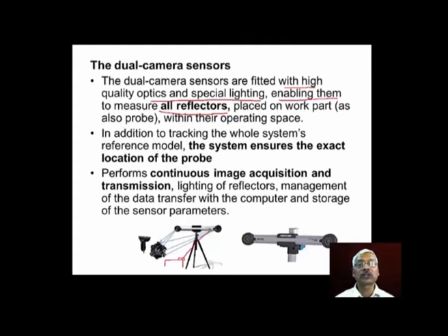In addition to tracking the whole system's reference model, the system ensures the exact location of the probe because of the triangulation technique used. The portable CMM system ensures the exact location of the probe with respect to the work part. It performs continuous image acquisition and transmission.